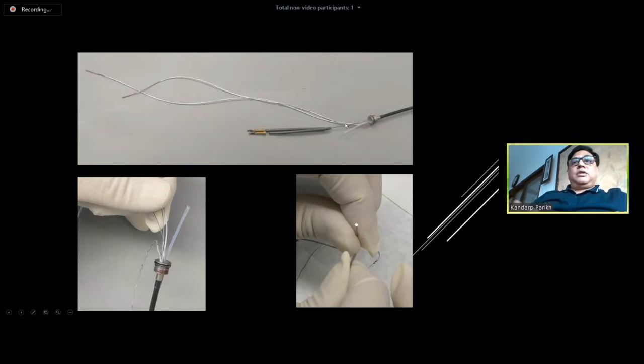So here you can see these two white thread-like structures. These are the bundles. One bundle is for the image transfer. This contains the fiber optic bundles for the image transmission, and another bundle is for the light transmission. This transparent cannula-like thing is an accessory channel. And there you can see 2 wires here with the adapters. These wires are responsible for the deflection of the scope. And these 2 adapters get connected to adapters coming from the handle. So you can snap it here, and that I'll show you. Here again, have a closer look. 2 wires, 2 bundles, and then 1 transparent thing, which is the accessory channel. Here this figure shows, if you put it across the light, you can see that there is a light. This is a light bundle.